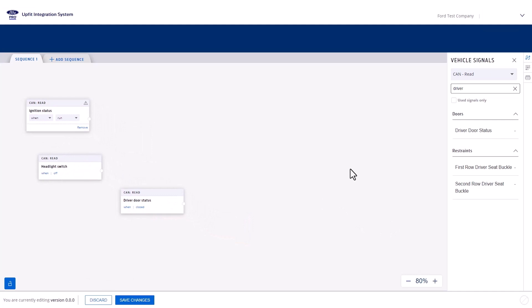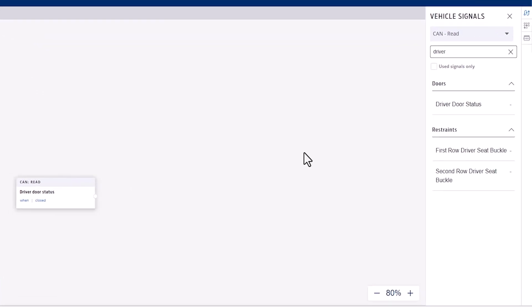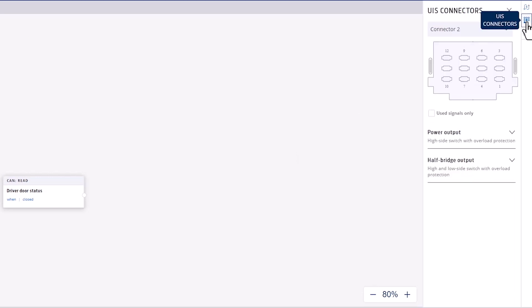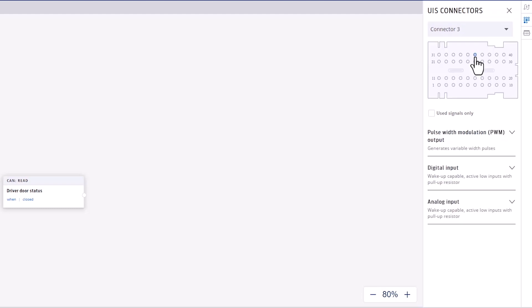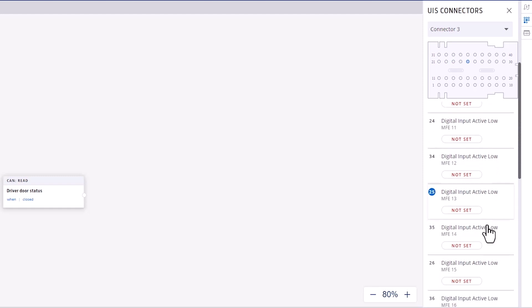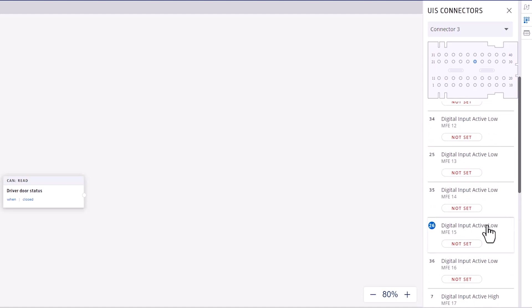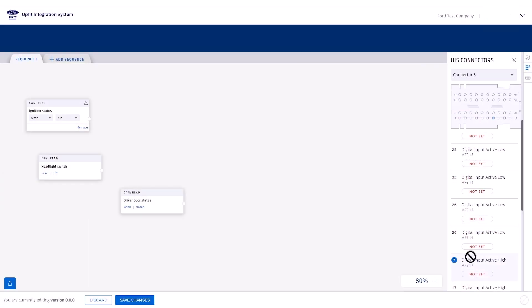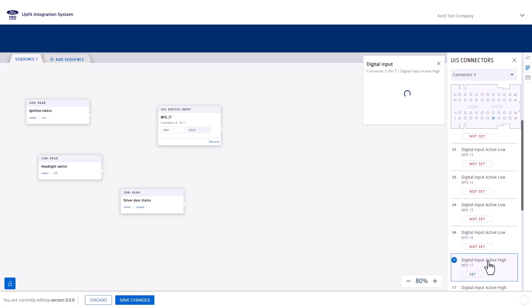To create logic for a hard switch in the logic tool, you need to wire it to one of the digital input pins on the UIS module. Navigate to the right-hand panel and select the UIS connectors tab. Choose connector 3 from the drop-down and then expand the digital input section. There are two types of digital inputs: active high and active low. Active high means voltage is applied when the signal is high; active low means ground is applied when the signal is high. For this example, we want an active high input. Select one and drag it onto the canvas. You can also double-click to rename the block — I'll name this one Beacon Light Hard Switch — and close to save.